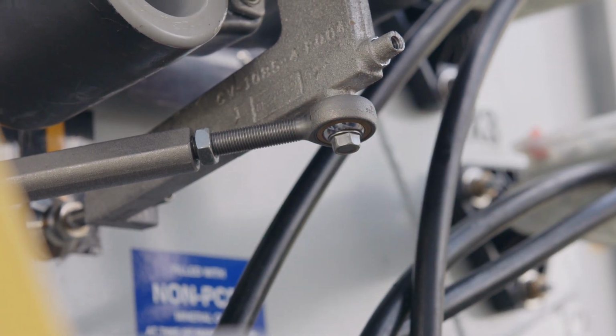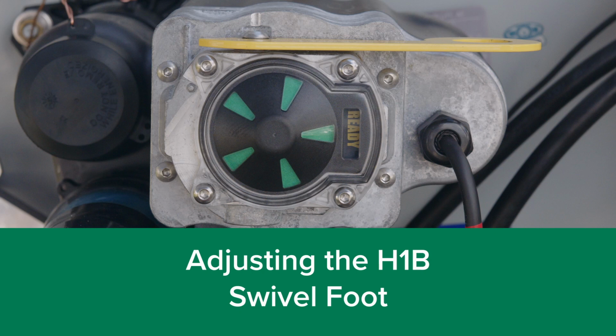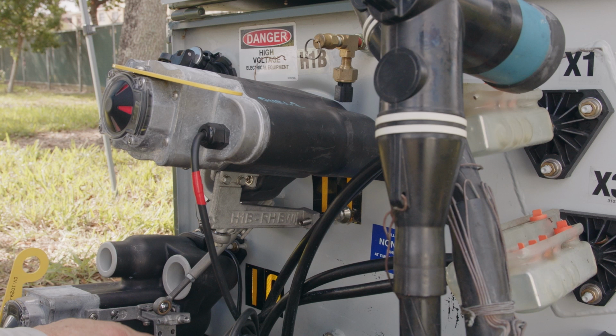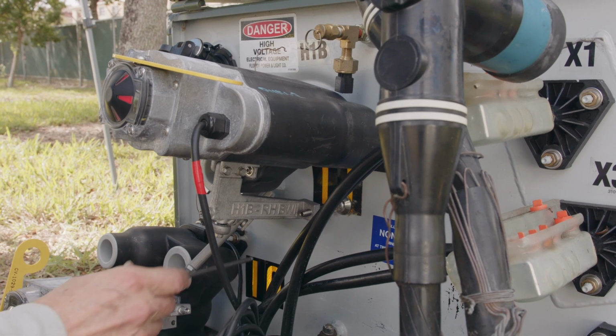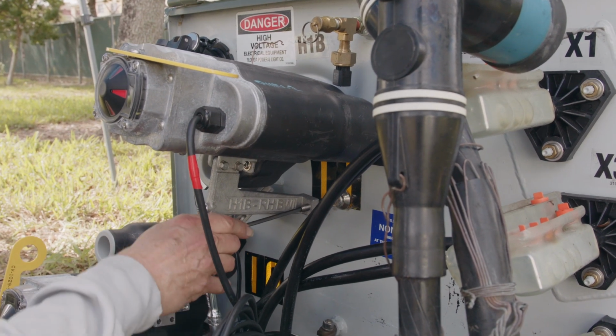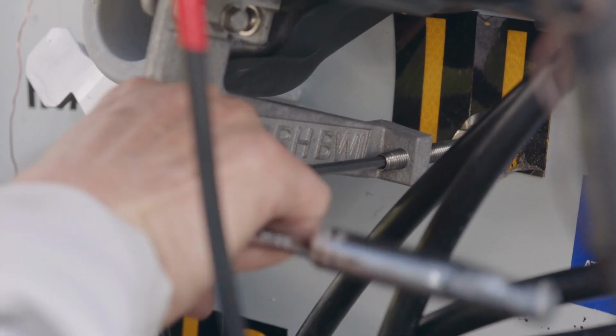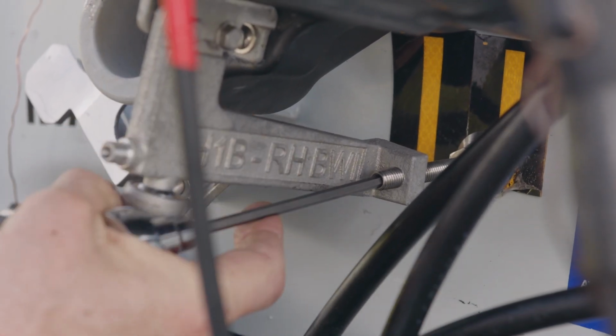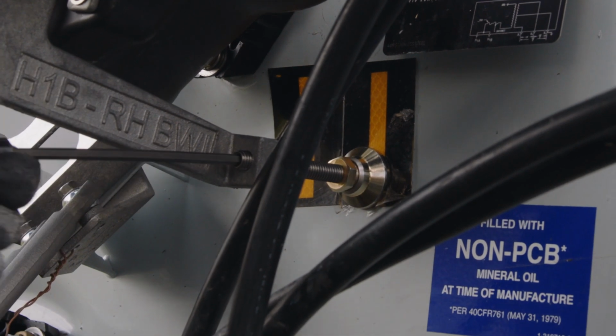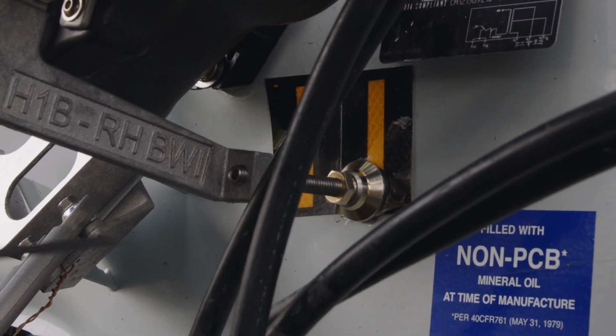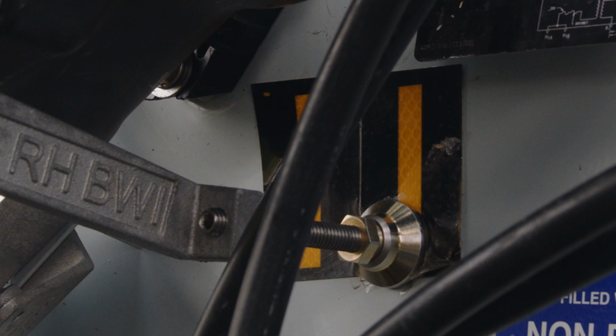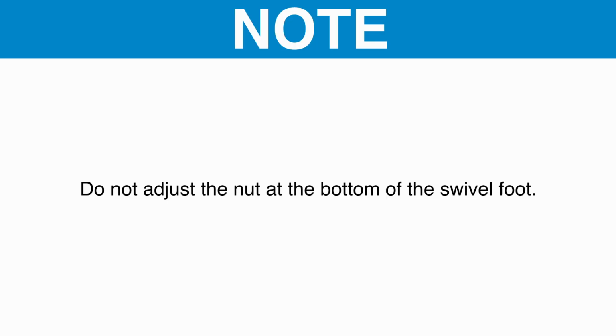To adjust the H1B bushing well interrupter swivel foot. Step 1. The top of the swivel foot is keyed for an Allen wrench. Tighten the swivel foot until it is hand tight against the transformer wall. Step 2. Tighten the swivel foot 2 to 3 additional turns tighter, 2 or 3 by 360 degrees, using a 3/16" Allen wrench to support the weight of the bushing well interrupter. Note: do not adjust the nut at the bottom of the swivel foot.